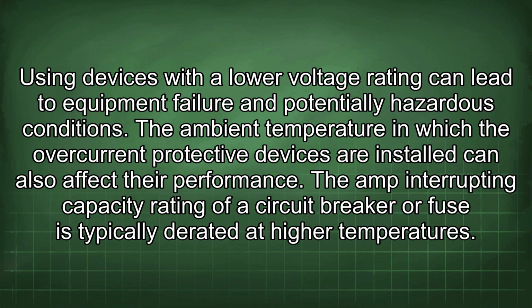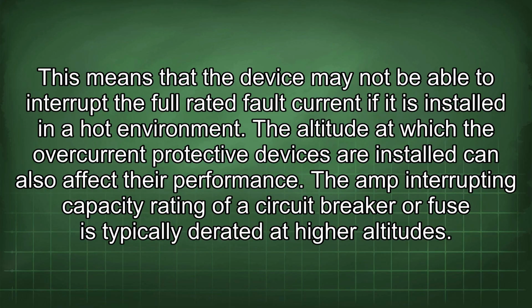The ambient temperature in which the overcurrent protective devices are installed can also affect their performance. The amp interrupting capacity rating of a circuit breaker or fuse is typically derated at higher temperatures. This means that the device may not be able to interrupt the full rated fault current if it is installed in a hot environment. The altitude at which the overcurrent protective devices are installed can also affect their performance. The amp interrupting capacity rating of a circuit breaker or fuse is typically derated at higher altitudes.